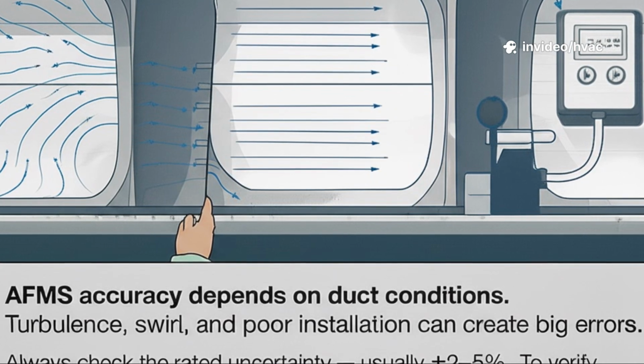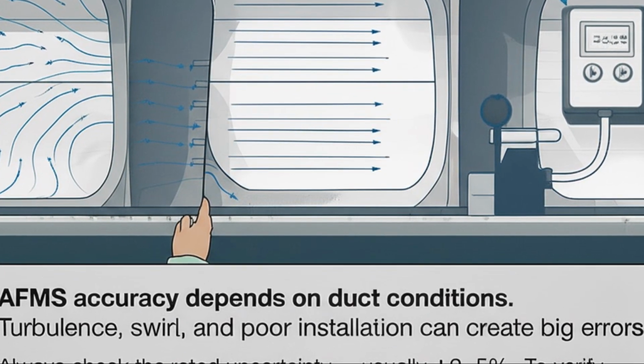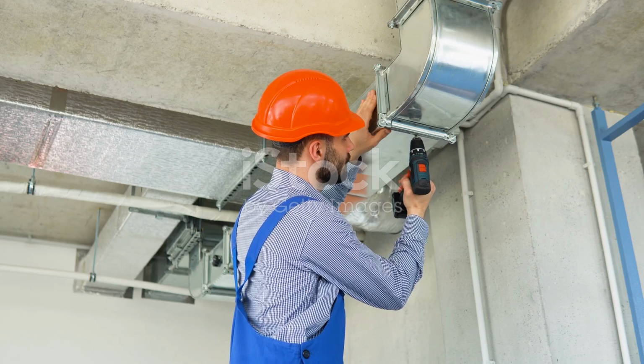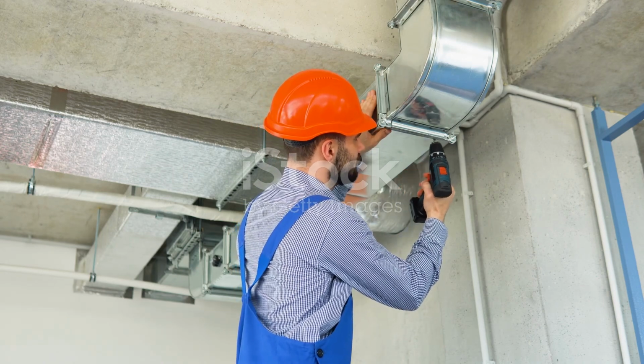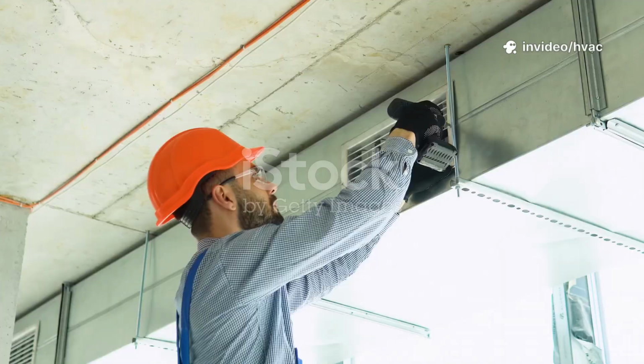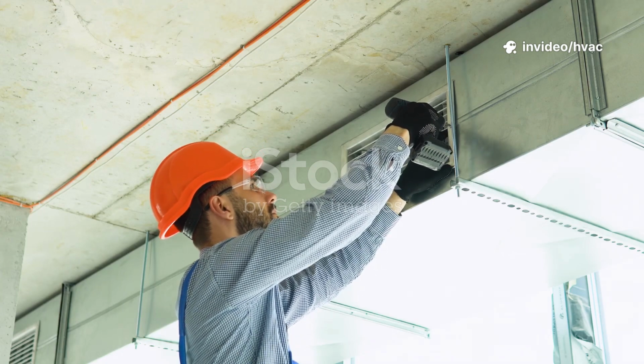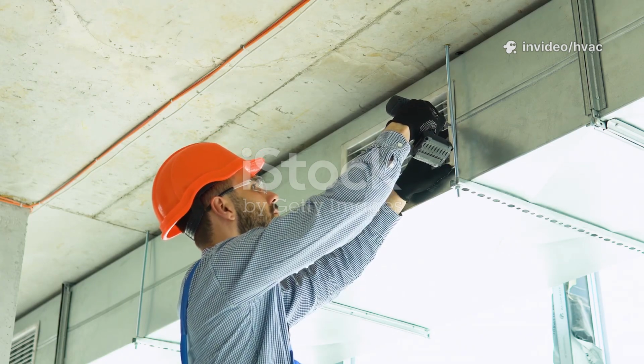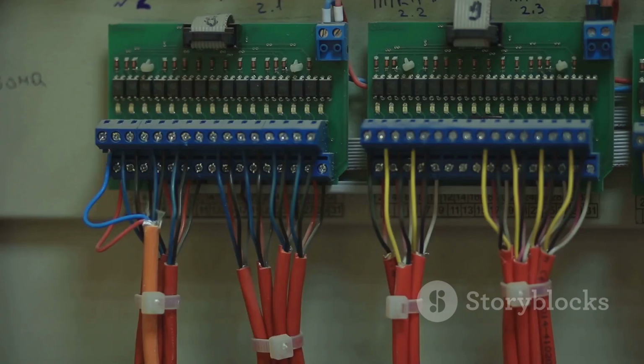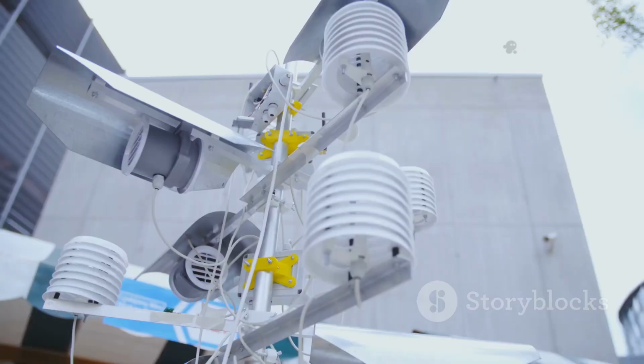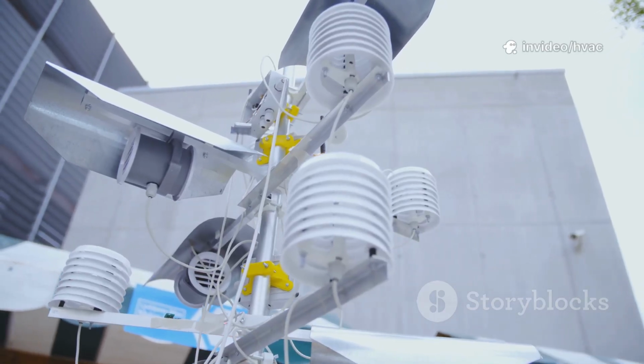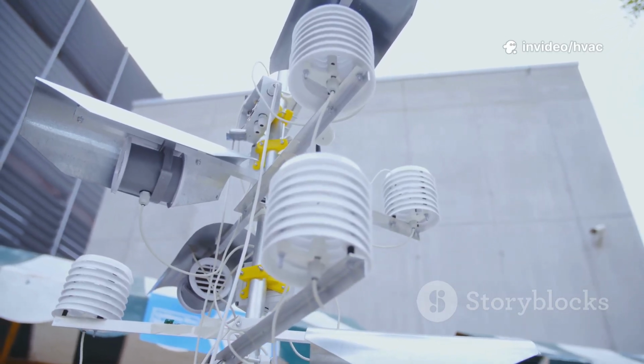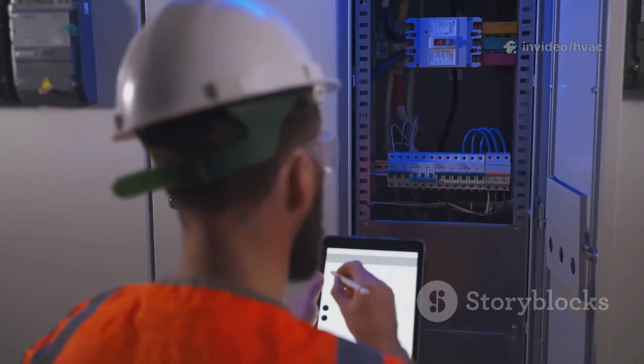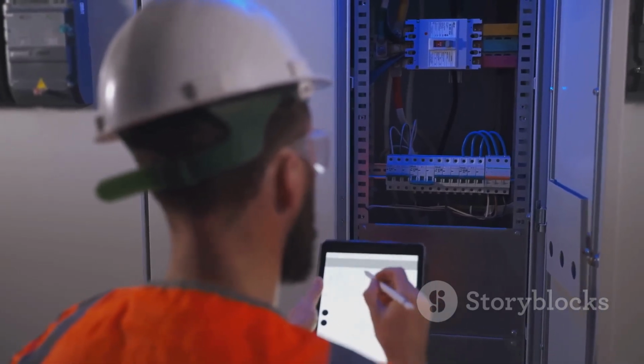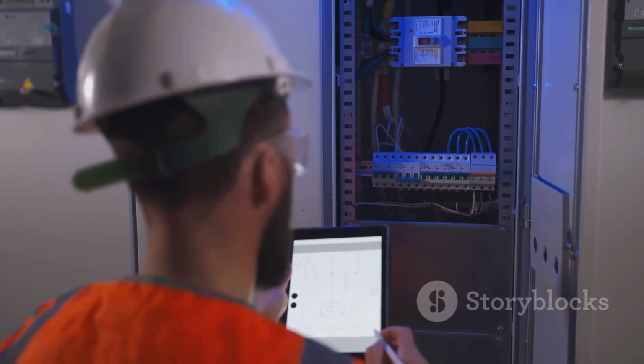Always match the AFMS type to your duct size, your expected flow range, and of course your accuracy needs. Make sure you verify that you actually have enough space for proper installation. And consider maintenance access. Sensors really need to be reachable for cleaning and calibration. Also, double-check wiring requirements and compatibility with your building management system to avoid integration issues. If your AFMS will be exposed to outdoor conditions, select weatherproof models to ensure long-term reliability. And finally, always confirm that your selection meets local codes and certification standards for safety and performance.